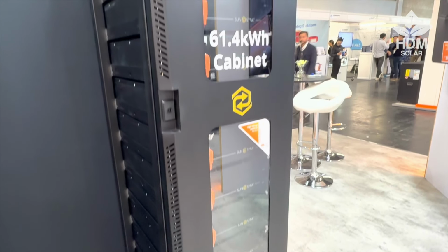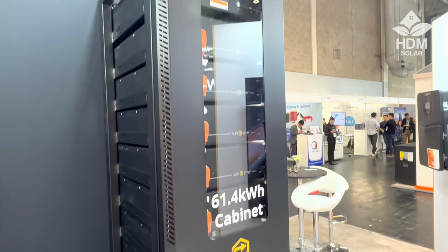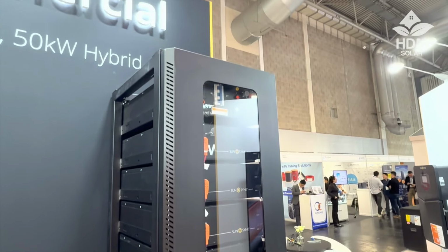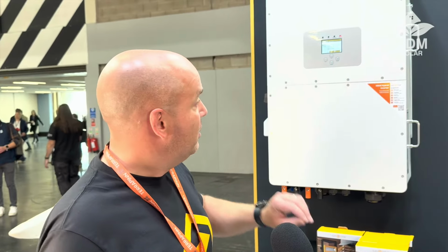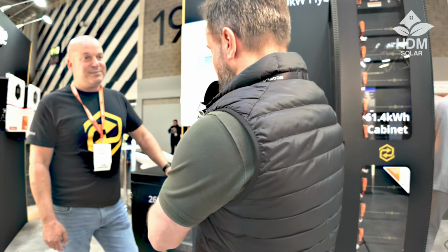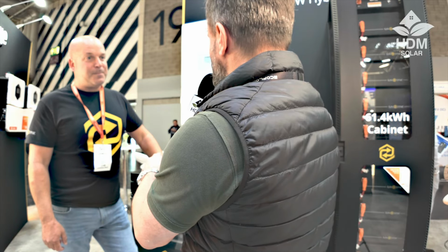You can have multiple stacks per inverter. The smallest amount per rack is 20 kilowatt hours, so you could have 4 batteries, fully scalable. All the commercial kit works on or off grid. The 50 kilowatt has an 80 kilowatt MPPT over 4 separate MPPTs with 8 strings in total, and a dedicated backup generator input. This looks impressive, but there's even more impressive stuff just around the corner.